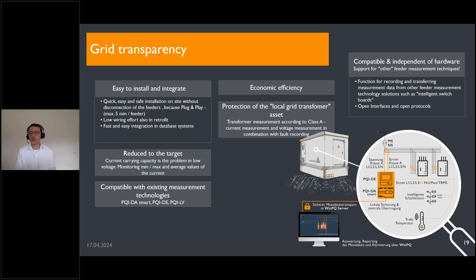Here are some examples from installations with this so-called iSense technology. You can see the device here installed directly at the cable with Rogowski coils, which are measuring the current, and the devices are installed in a daisy chain, really easy, and the master is installed directly at the local transformer station, evaluating and measuring all this data.